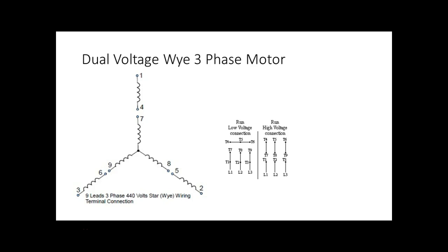But what we do is connect the motor in series. For low voltage we hook them in parallel, right? And for high voltage we hook the coils in series. Now on our motor, they're not labeled 1, 2, 3, 4, 5, 6, 7, 8, 9. They're labeled T1, T2, T3, T4, T5, T6, T7, T8, T9. And these are terminal numbers.